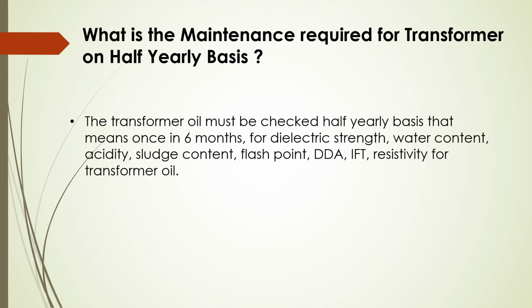What is the maintenance required for the transformer on half-yearly basis? The transformer oil must be checked half-yearly basis. That means once in 6 months for dielectric strength, water content, acidity, sludge content, flash point, DDA, IFT, resistivity for transformer oil.